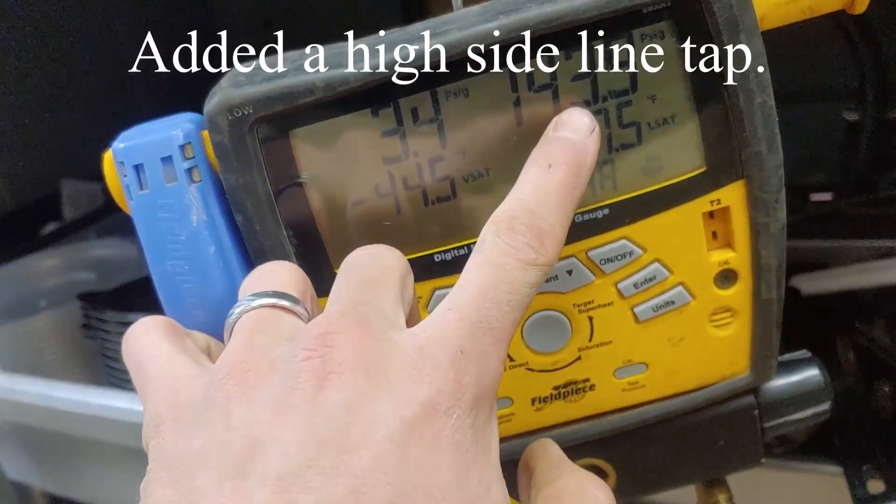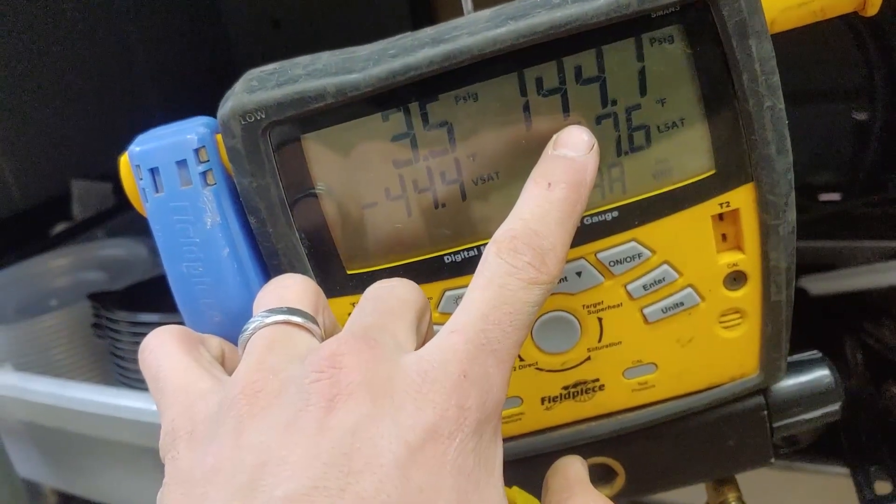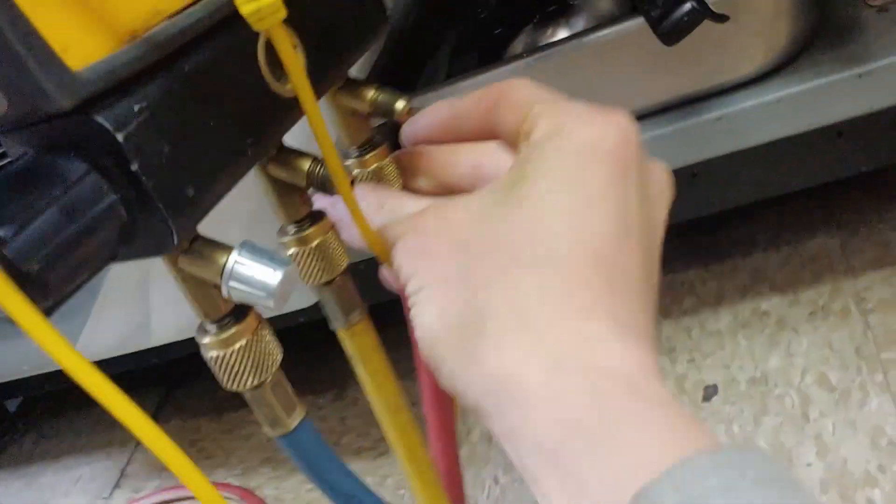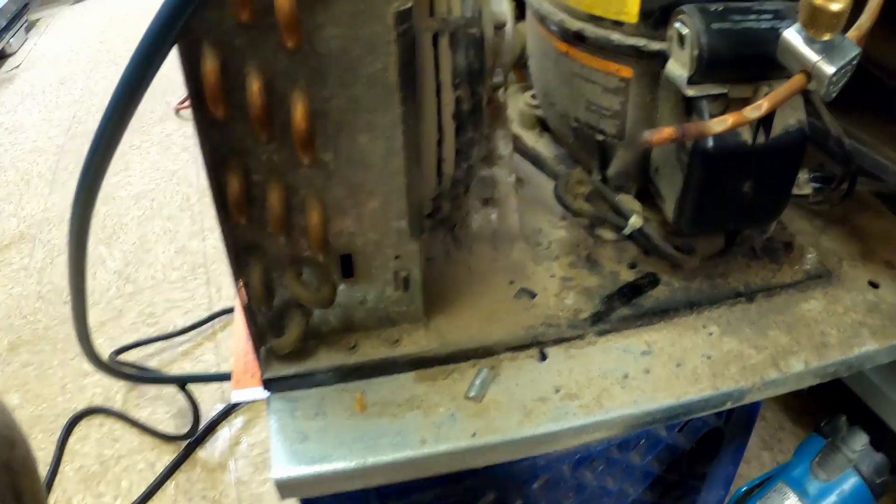You can see we've got almost 150 psi on the high side and only 3 on the low, so we know that the liquid's not getting through the compressor. It's just sitting in this coil and it's not going anywhere else. And we probably have straight liquid here, so we're going to get that recovered. So we're down to 3 psi on the low side.